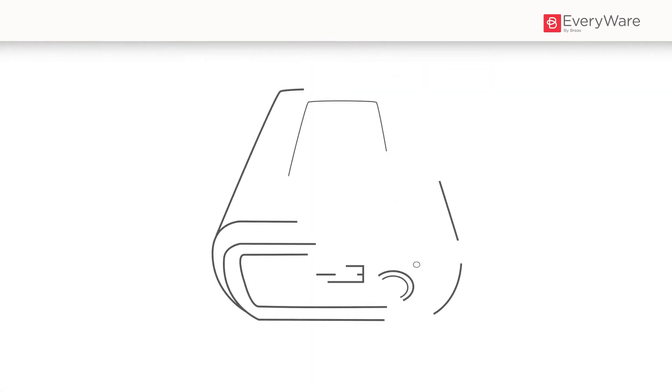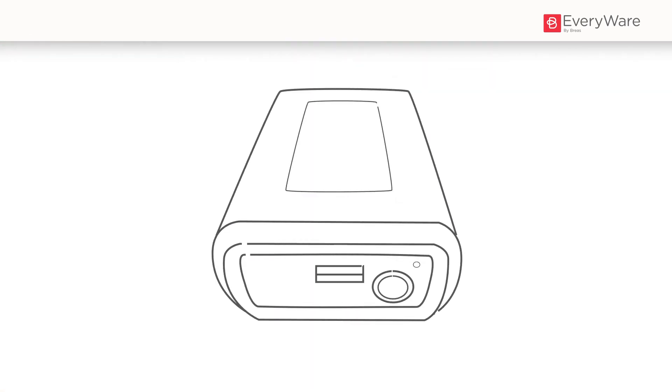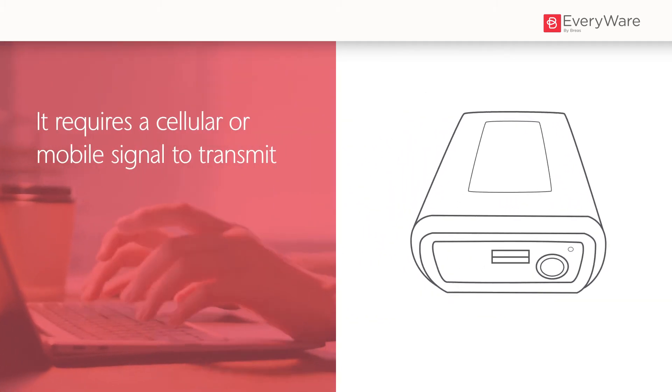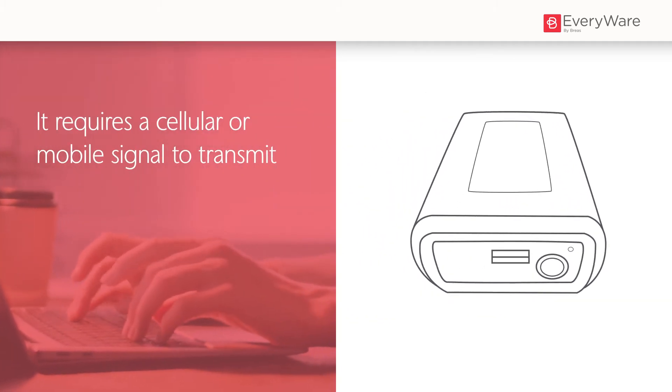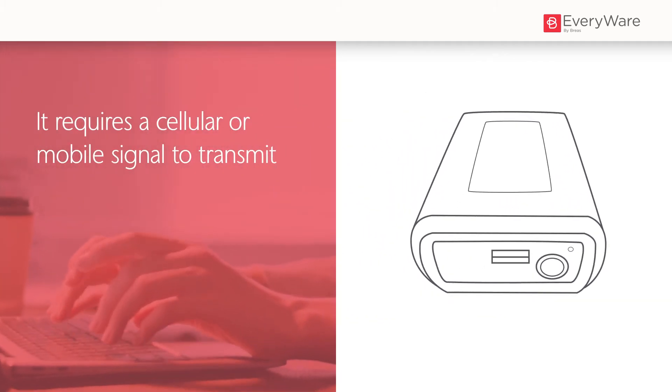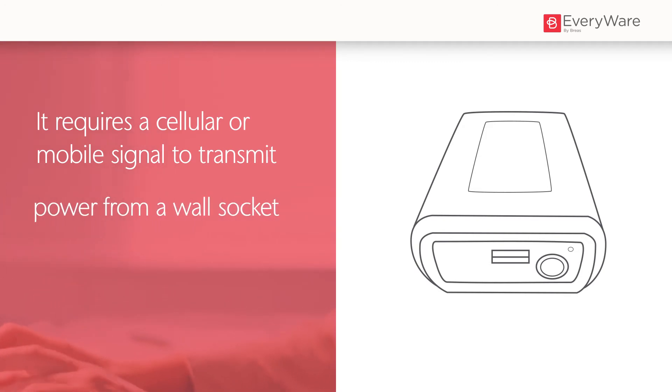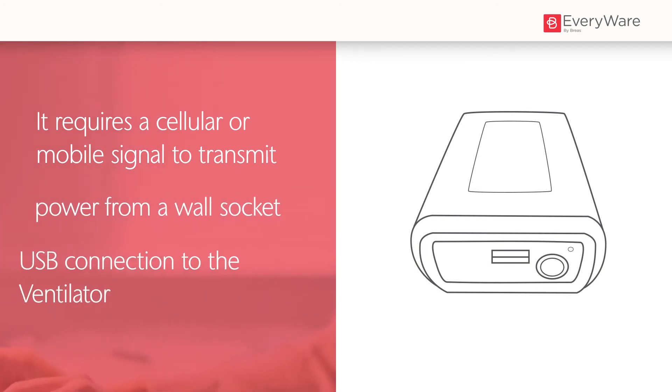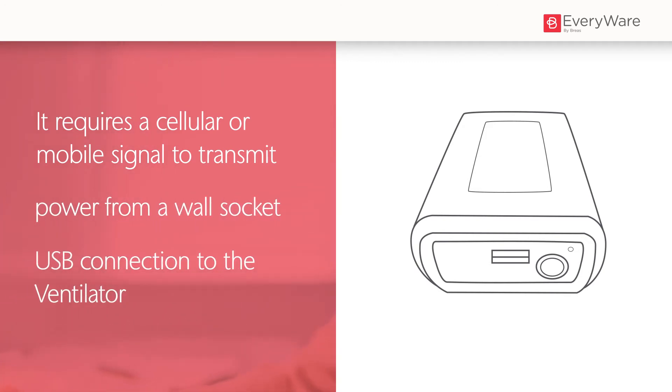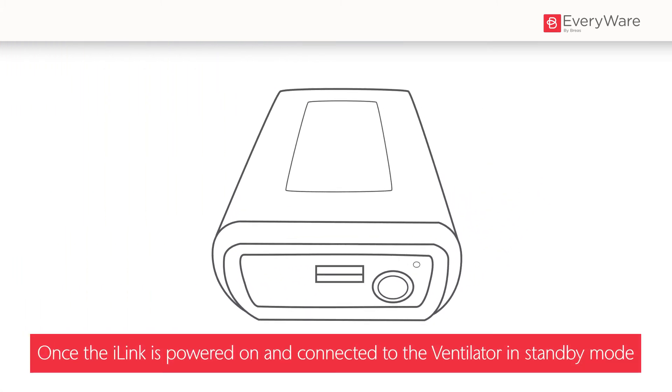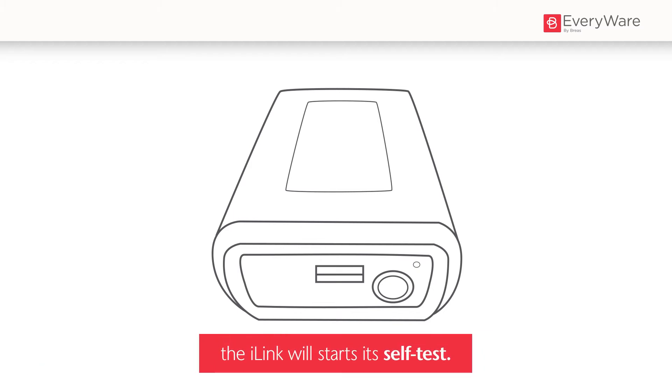The i-link modem is used to securely transmit data from the Breas ventilator to everywhere. It requires a cellular or mobile signal to transmit, power from a wall socket and a USB connection to the ventilator. Once the i-link is powered on and connected to the ventilator in standby mode, the i-link will start its self test.